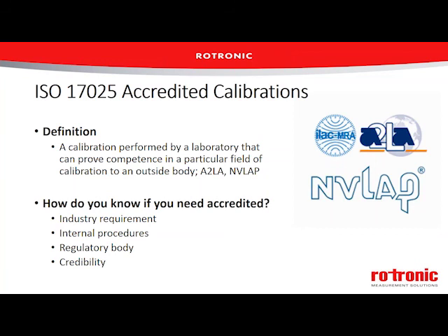They actually have to do what's called proficiency testing or interlaboratory comparisons to ensure that their readings are reasonable and within their uncertainties. But there's also a technical expert that would come from an organization like NVLAP or A2LA who come in and audit these laboratories to ensure that they've got the processes in place, that they understand how to do measurement uncertainty estimations, that they've got the proper equipment in place and they know how to use it.